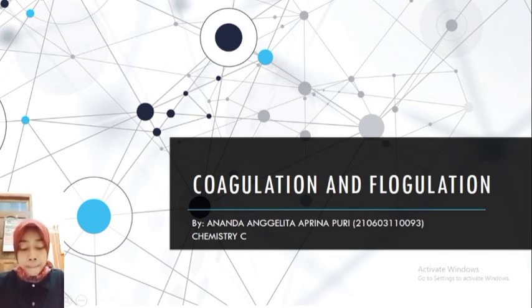Operators may need to add alkalinity for coagulation to be effective when using iron or aluminum coagulants that can consume alkalinity and depress pH when they are added to low alkalinity waters.